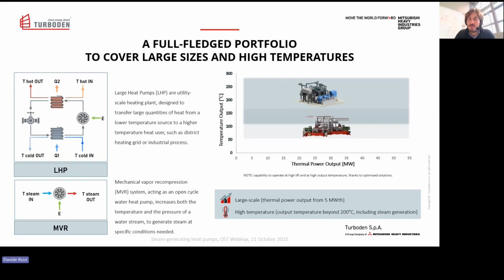In terms of temperature, we can start for heat pumps from 80 degrees C onward, up to more than 250 degrees C if we are referring to steam. I think when referring to steam it's better to talk about pressure - we can provide solutions up to 30 bar G steam if we are coupling a steam compressor to our heat pumps. Our portfolio is basically composed of customized solutions. We do not have an off-the-shelf product; we design the plant, because above a certain size a heat pump becomes more a plant than a package. So we design the plant together with the client and tailor-make the solution.